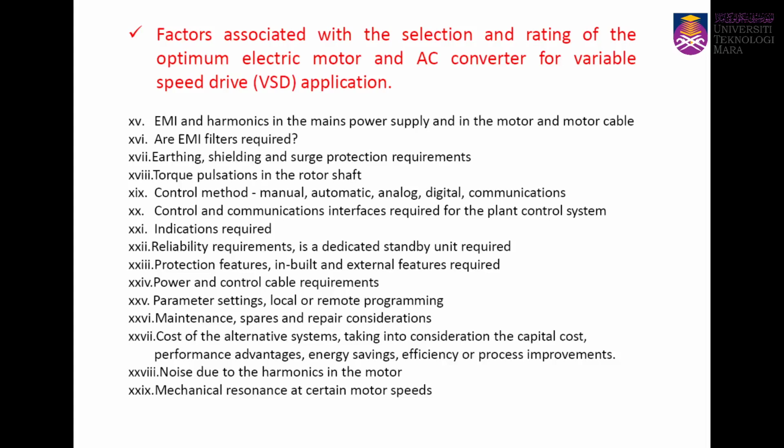So we need to look at some of the limits, the standards that you need to comply with. And are EMI filters required? So you have to look at earthing, shielding, and surge protection requirements, torque pulsation in the rotor shaft, and the control method: is it going to be manual or automatic, analog or digital, and is there any communication that you need to do with the machines?